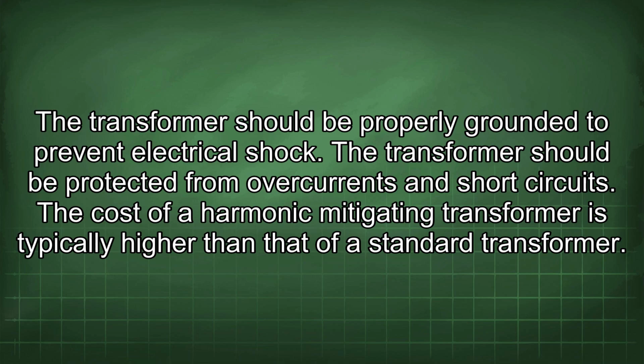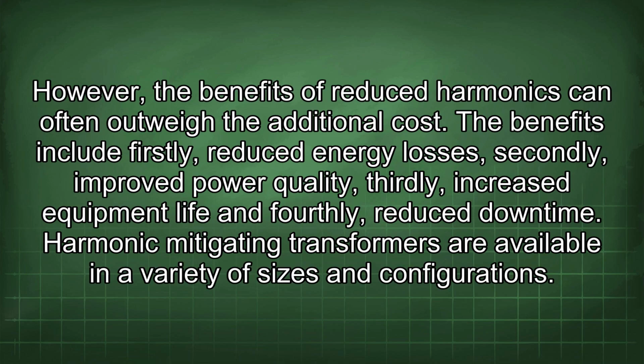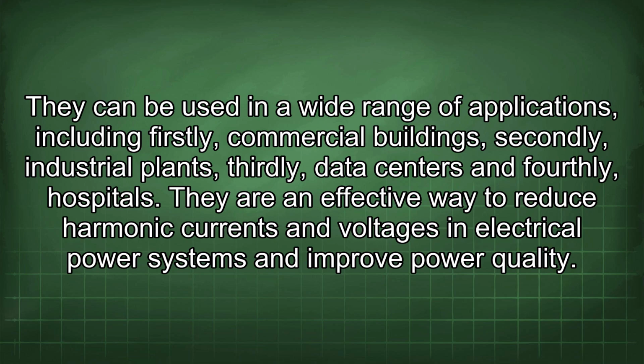The cost of a harmonic mitigating transformer is typically higher than that of a standard transformer. However, the benefits of reduced harmonics can often outweigh the additional cost. The benefits include firstly, reduced energy losses, secondly, improved power quality, thirdly, increased equipment life, and fourthly, reduced downtime. Harmonic mitigating transformers are available in a variety of sizes and configurations. They can be used in a wide range of applications, including firstly, commercial buildings, secondly, industrial plants, thirdly, data centers, and fourthly, hospitals. They are an effective way to reduce harmonic currents and voltages in electrical power systems and improve power quality.